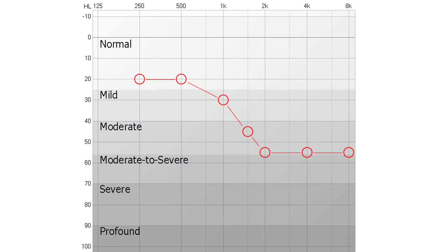Now let's talk about performance. Performance of a hearing device is something we can objectively test, just like I would test a hearing aid to see how well it's programmed. The method I'm gonna use is called real ear measurement. This allows me to see if these devices are capable of meeting a mild to moderate hearing loss prescription. They will also let me test whether the noise reduction feature is working and how well it works. Since the Otofonix Elite is supposed to be appropriate for a mild to moderate hearing loss, we're going to check its capability of meeting an NAL NL2 prescription for a mild to moderate hearing loss.